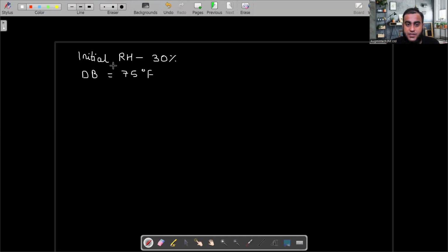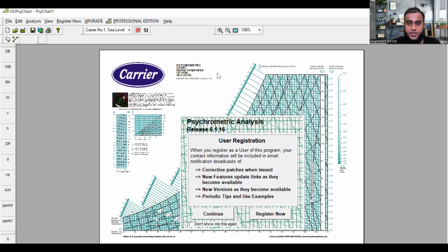Now, based on this initial relative humidity and this dry bulb temperature, we can get the value of the humidity ratio. From where? From the ASHRAE psychrometric chart, or if you have software. I will show you with the help of software. Here I have psychrometric software. Can you see my page? The software is visible. When you open this software, you will get this type of interface.